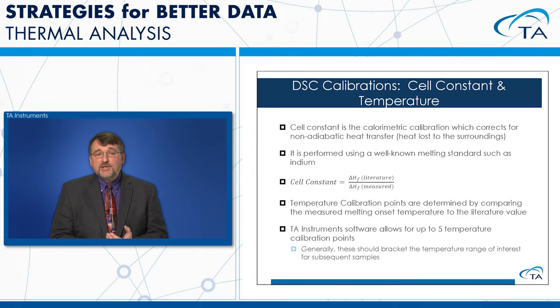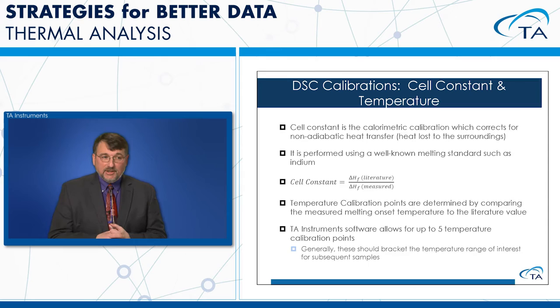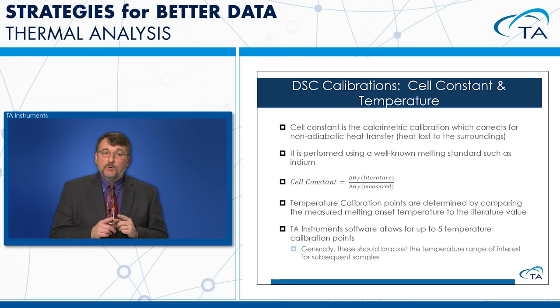Cell constant and temperature calibration are done by running a sample with a known value, like indium. The cell constant corrects for any heat loss to the surroundings, determined by comparing the measured heat of fusion to the literature value of indium. For temperature calibration, we compare the measured DSC onset temperature to the literature value. Both can be done in a single indium run, though our software allows up to five temperature calibration points.